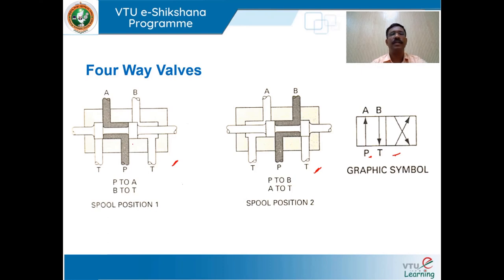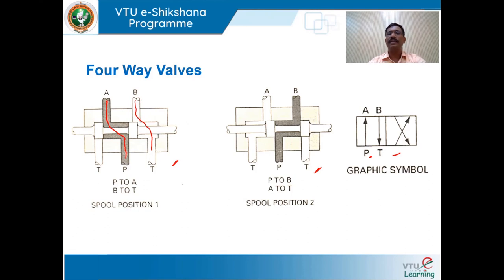In spool position one, P is connected to A and B is connected to T. That is, the pump line connects with output port A and output port B connects with the tank line. A line with an arrow denotes the flow direction, so P is connected with A and B is connected with T.